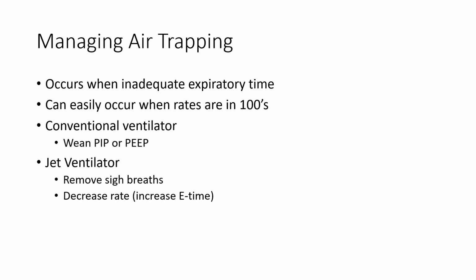Air trapping primarily occurs when there is not enough time for exhalation for a breath before the next breath begins. Since the jet delivers respiratory rates in the hundreds, air trapping is a valid concern. In conventional ventilation, when air trapping is present, the PEEP is decreased. During jet ventilation, when air trapping is present, the first strategy is to remove the sigh breaths, if present. Next, the jet rate is decreased. This would allow more time for exhalation.